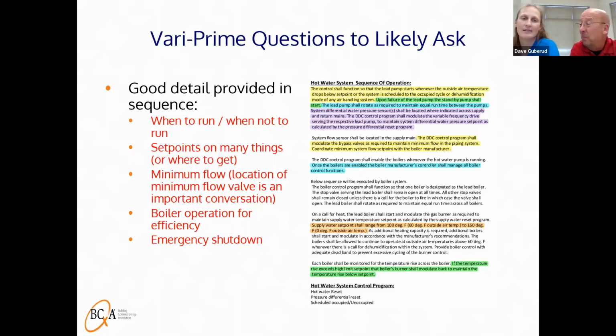Yes, and then boiler efficiency. Oftentimes boilers like to operate, they'll find that they're most efficient when maybe all 3 boilers are running. So now when you have 3 boilers running, you have 3 times your minimum flow, versus if one ran to capacity and then brought on the second. So you really need to have your minimum bypass valve. You have to be able to accommodate that minimum flow in whatever manner those boilers are going to operate.